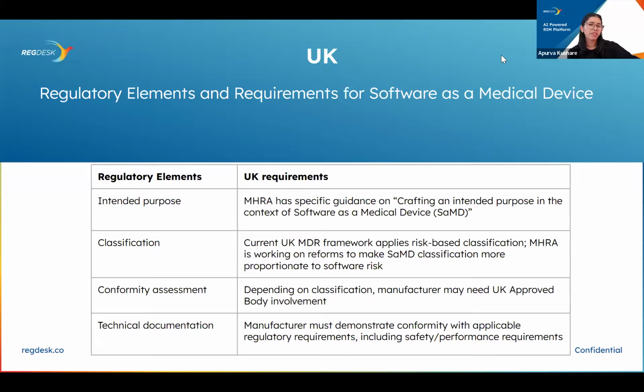And I would like to talk a little bit more on the intended purpose. So in the UK, there is a specific guidance on intended purpose, and they have clearly defined some key elements to consider when defining the intended purpose of the device. So the key elements include the structure and function of the device. It should include the intended population, the intended users, and the intended use environment.